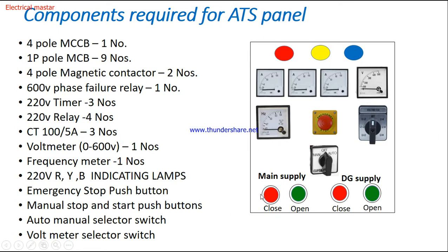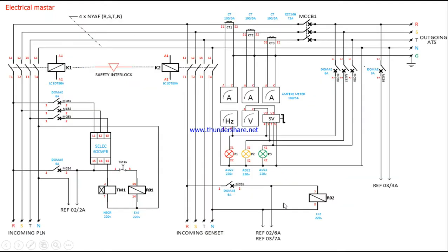Now let's look at the ATS panel wiring diagram. First I will explain the power diagram, then the control diagram. The incoming from the electricity board is connected to contactor K1, and the incoming from the diesel generator is connected to contactor K2. Whenever the K1 magnetic contactor is energized, it supplies directly to the load breaker.